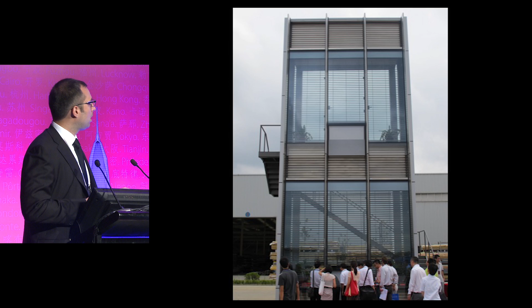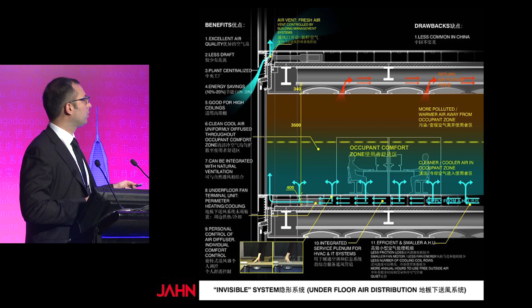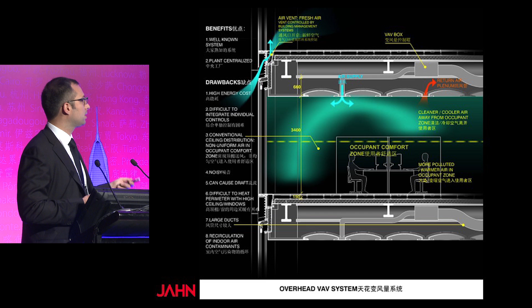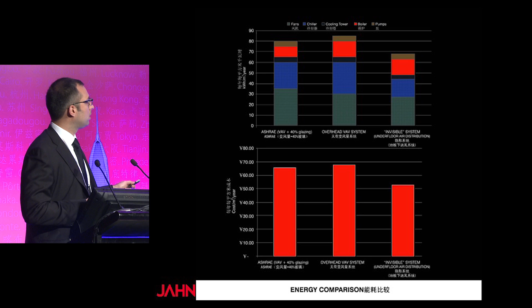The office floors use underfloor air distribution. This helps the air system work with the convective movement of air, since heat from people and computer loads rises. This works much more efficiently than a traditional VAV system, and these graphs show the energy reduction from a VAV to an underfloor system.